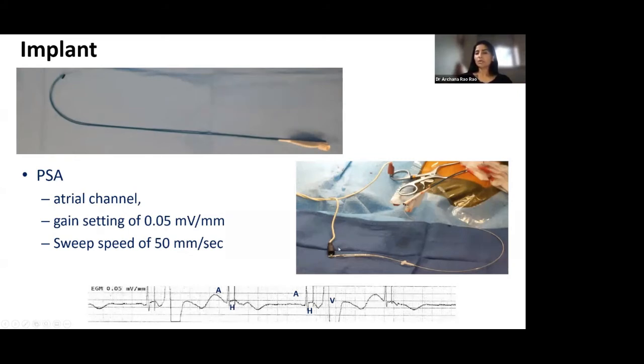Also note that when you're deploying, this lead needs to be measured in unipolar configuration, because the distal screw of the lead, the helix, is the cathode. So we tend to measure this in a unipolar configuration with the black on the tip and the red of the anode attached to the pocket itself. And even as you advance the catheter, the lead tip is just outside, and as it makes contact through a blood film onto the area of interest, you should be able to see the His spike coming through.